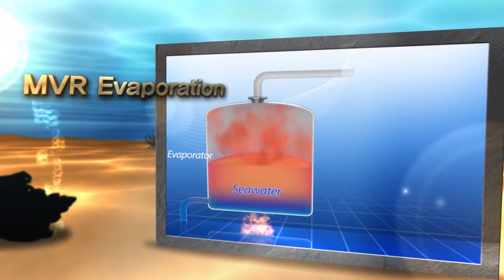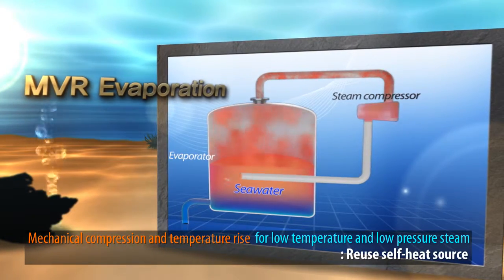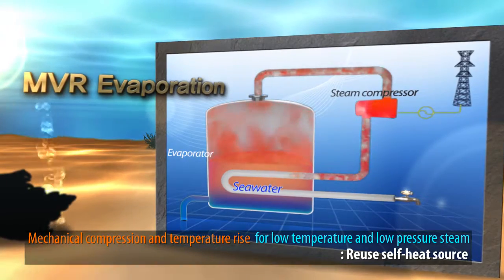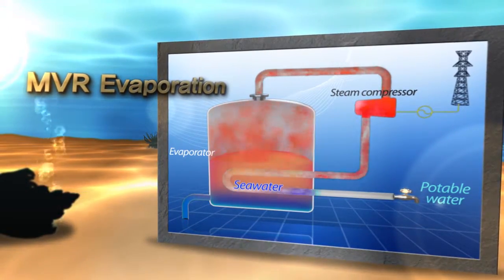MVR evaporation corrects these flaws by pressurizing evaporating steam and raising the temperature of the steam with an electric compressor instead of burning fuel, and reusing the heat source through an embedded heat exchanger to minimize energy use.